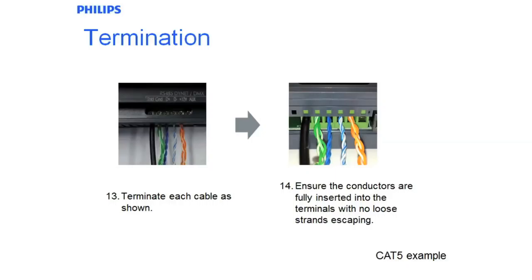If we have a look from left to right, we should see the drain going into the shield terminal along with our PVC shielding. We should see the green and green-white with both our ingoing and outgoing cables going into the ground termination. The blue of each blue pair is going into the D-plus. The blue-white of each blue-white going into our D-minus terminations. And the orange and orange-white combined together from each of our ingoing and outgoing cables going into the plus-12 connection.